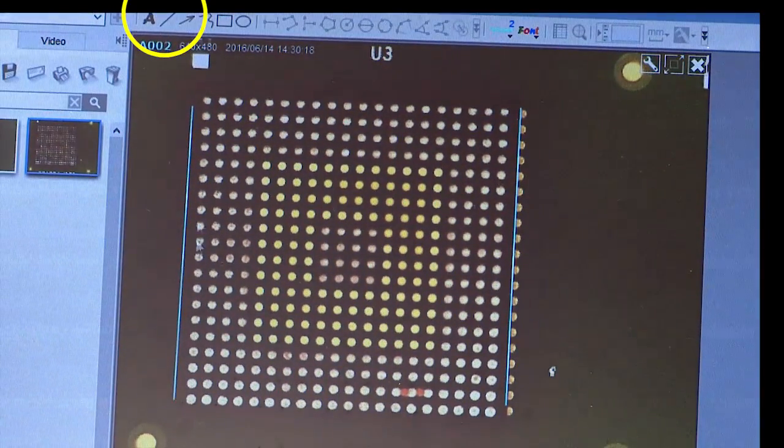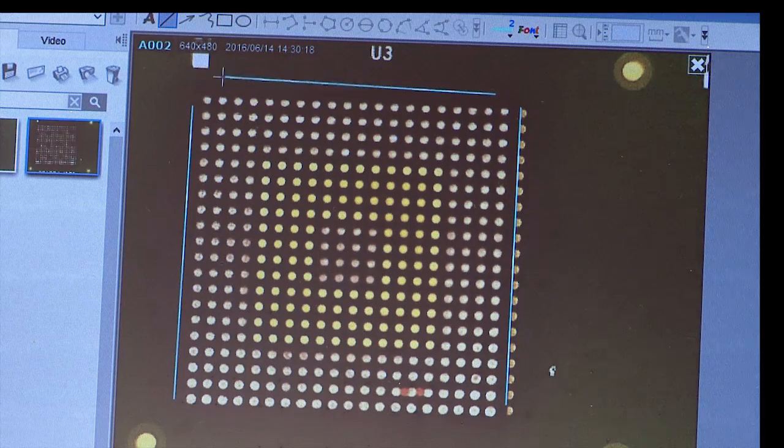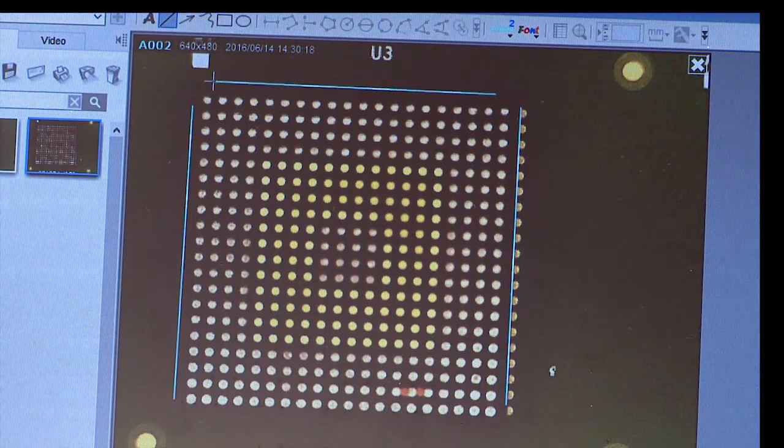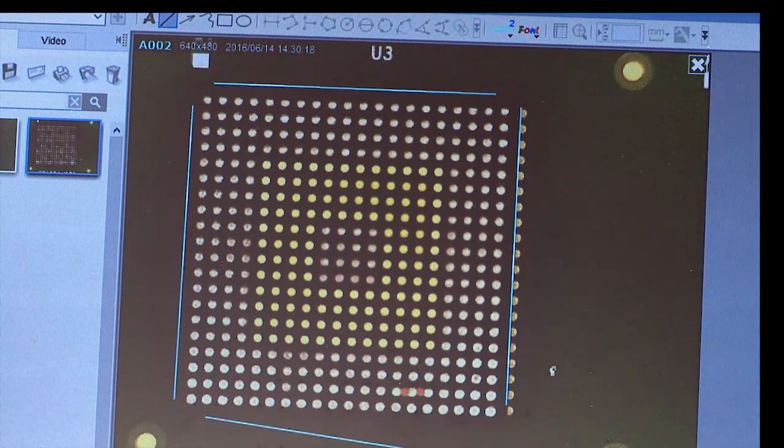With the software tools, draw lines to identify the four edges of the component. These guide marks will provide a reference that can be used to manually align the component package to the transparent image that is overlaid over the array.